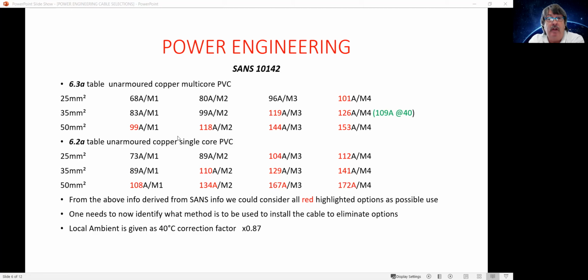So if we have a look for our 100 amp base supply, 25 mil, 35 and 50 mil appear to be the type of product that we would be looking at, just looking at the numbers. I've highlighted all the areas where the potential for around about the 100 amp supply would be met with the cables. And we can see that under some construction, we would get a 25 mil cable at M4, 101. And the same would be up to 153 amps with a 50 mil.